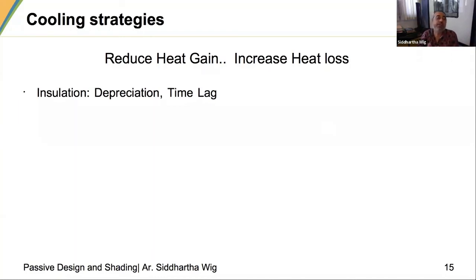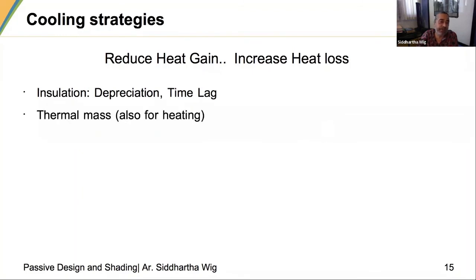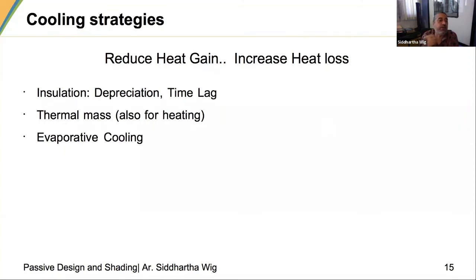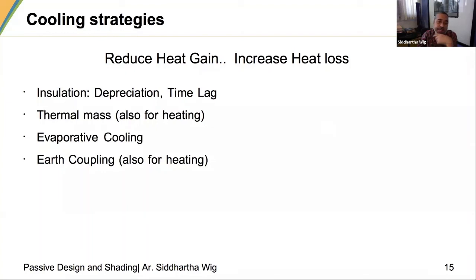At times there may be a variation of strategies you could apply for achieving the same level of comfort. Thermal mass is important — it can be used for both cooling and heating. Evaporative cooling works very well where water is available; we have used it for misting and simple evaporative cooling. Earth coupling — whether berming, sunken windows or embedding the building in the ground — can be achieved in a lot of different climatic zones, though there can be construction, buildability and maintenance issues.